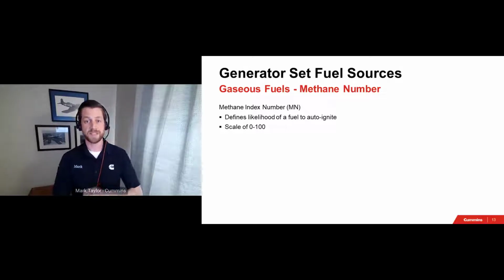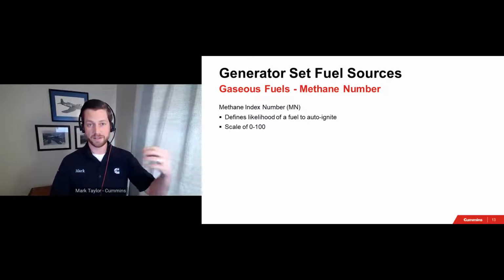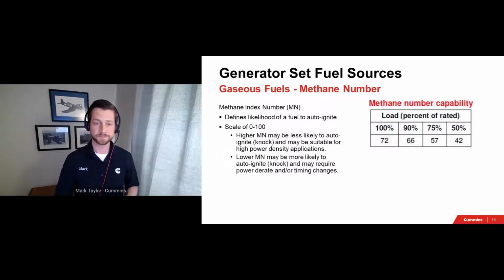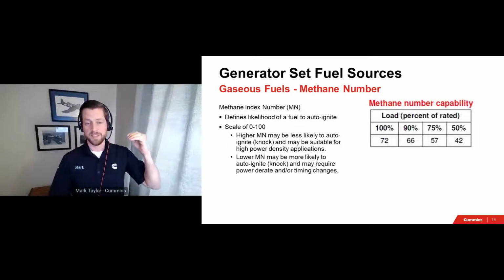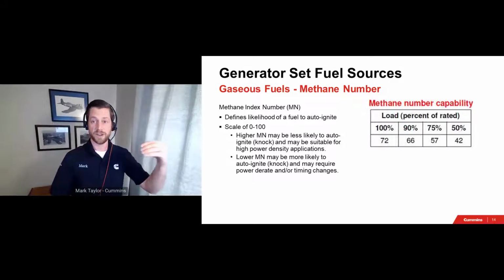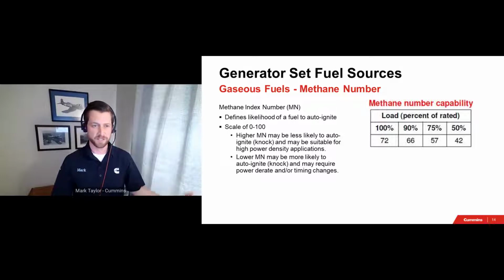This value describes how likely a fuel is to combust uncontrollably, creating knock or pinging in an engine. On a scale of 0 to 100, a methane index number that is higher may be less likely to lead to engine knock, where a lower value may be more likely to provide issues with engine performance. Correlating this into practical terms, a lower methane index number may mean a gaseous fuel generator set may incur a power derate. This table that I have shown here is an example from one of our own products.